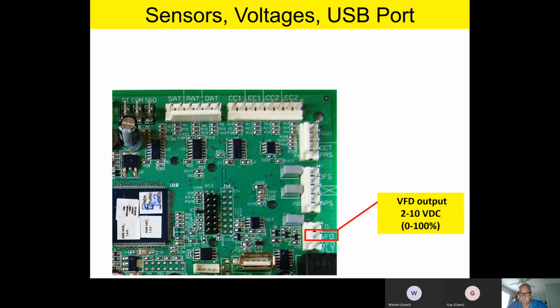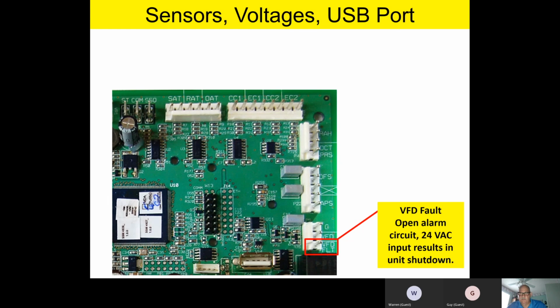Right down below that, you'll have a VFD alarm. Now, it should be noted this is an open alarm circuit, which means a 24-volt input. A 24-volt input to that VFD fault results in unit shutdown. So let me say that one more time and stress this. This is an open alarm circuit, which means that when it's normal, there's nothing there. There's no voltage on there, normal condition. But if I have an alarm, my VFD will output 24 volts.